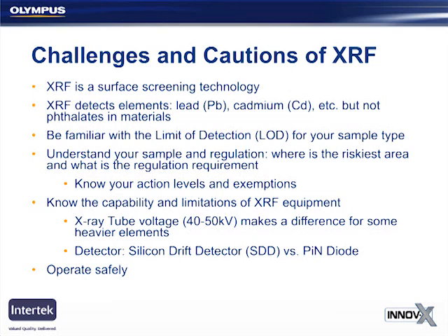XRF is an elemental testing technique, so it's great for testing lead, cadmium, and other restricted elements, but as Joe mentioned, it's not compatible with testing phthalates in materials or finding out what kind of flame retardant you have in your material. You need to use other testing methods to get that information. You want to be familiar with what detection limit you are going to be seeing for your sample type and make sure that your screening level is realistic based on that detection limit.